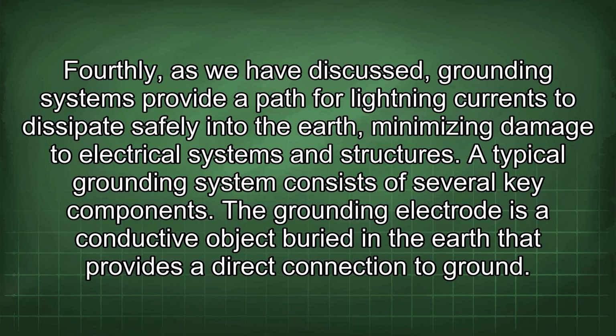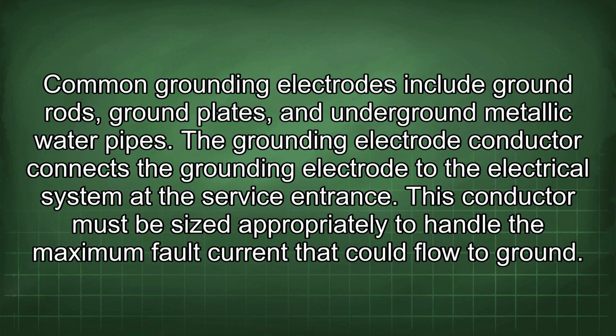Fourthly, as we have discussed, grounding systems provide a path for lightning currents to dissipate safely into the earth, minimizing damage to electrical systems and structures. A typical grounding system consists of several key components. The grounding electrode is a conductive object buried in the earth that provides a direct connection to ground. Common grounding electrodes include ground rods, ground plates, and underground metallic water pipes.